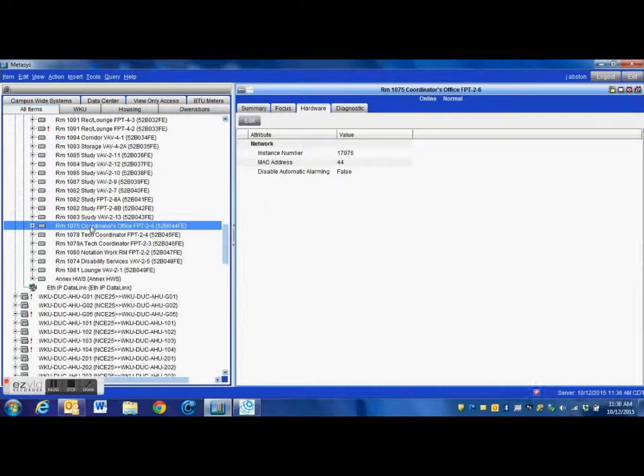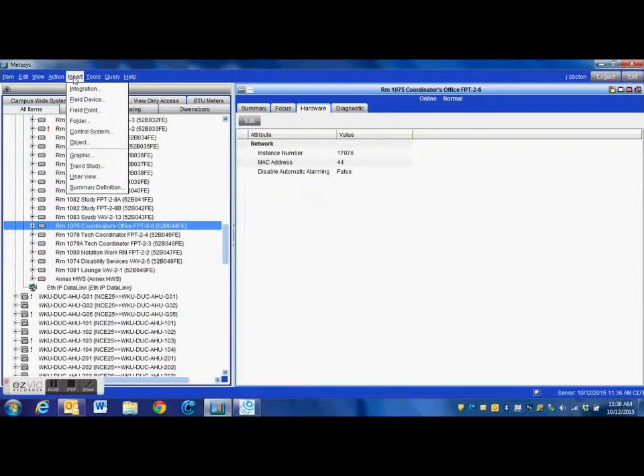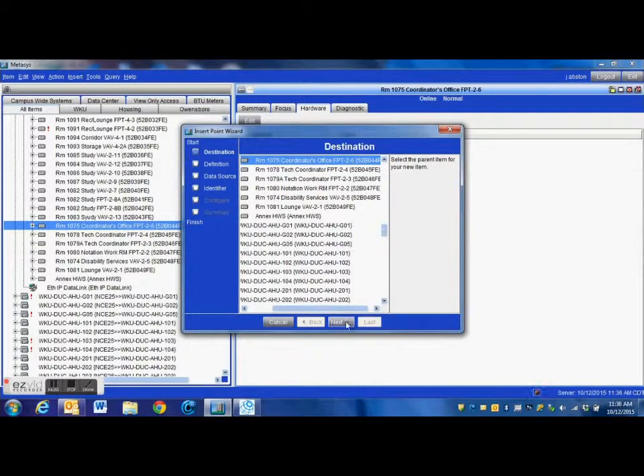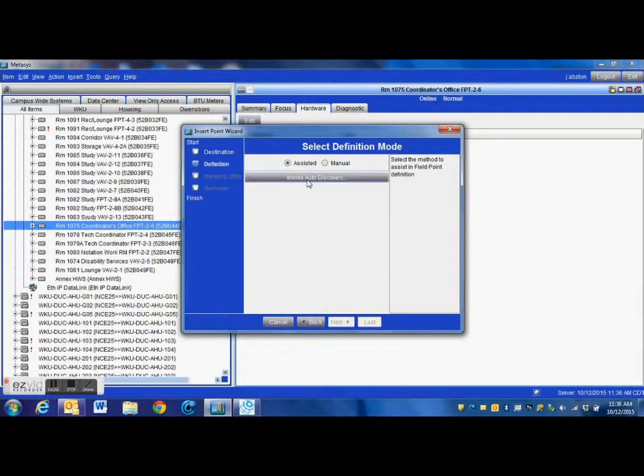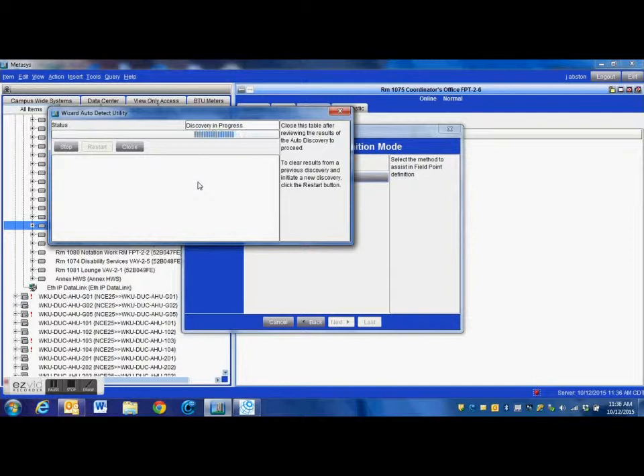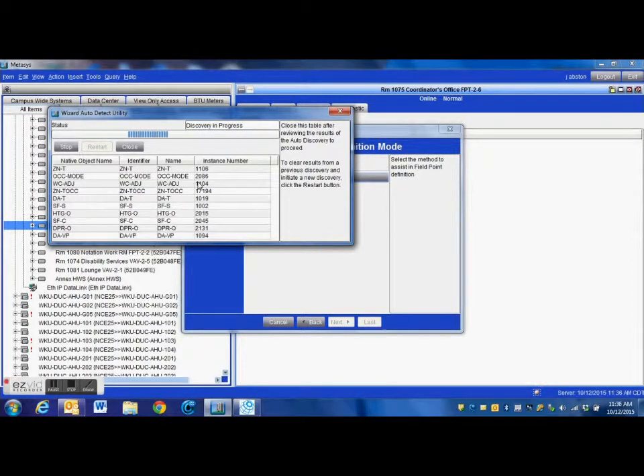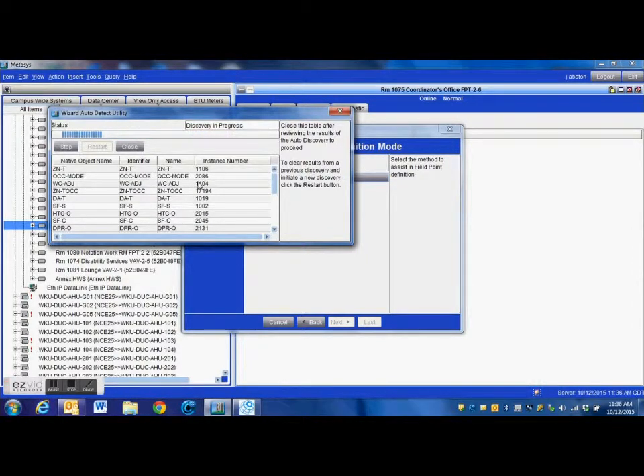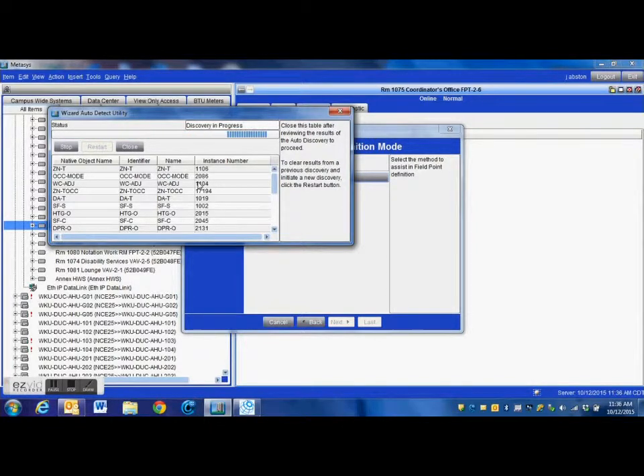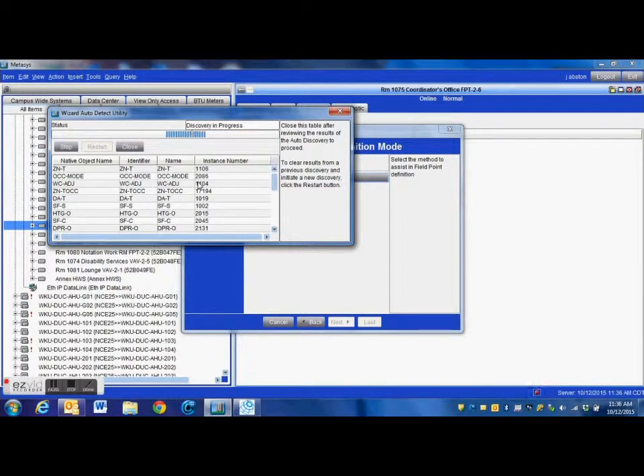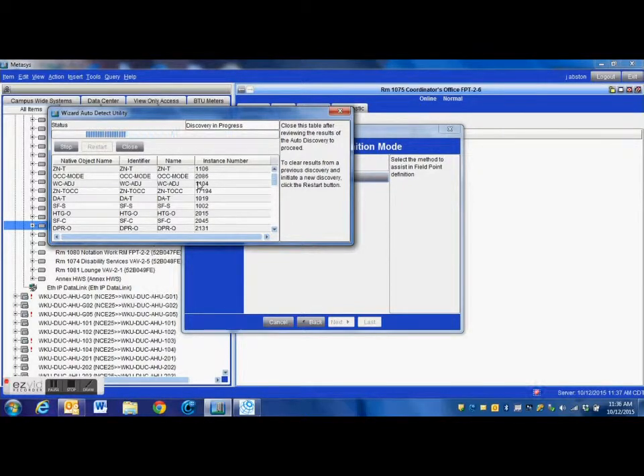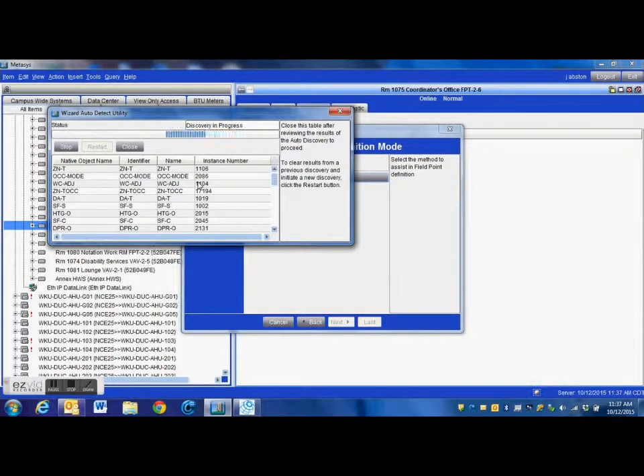I'm going to highlight the particular VAV and go up to insert field point. Since this is a BACnet controller, I can use the auto discover feature which saves us a lot of time. I'm going to let that run. It's going to populate all the points that are exposed in this particular controller. Once it finishes its scan, we will just close this window.